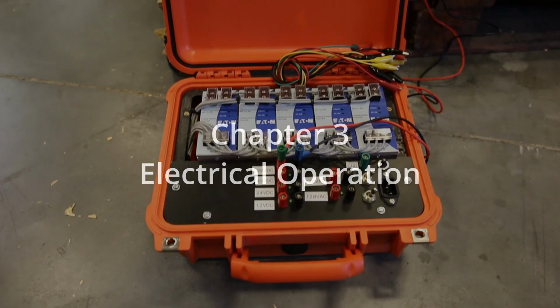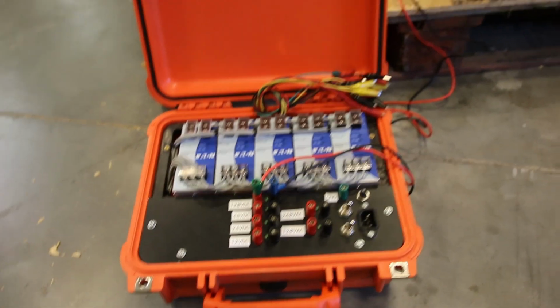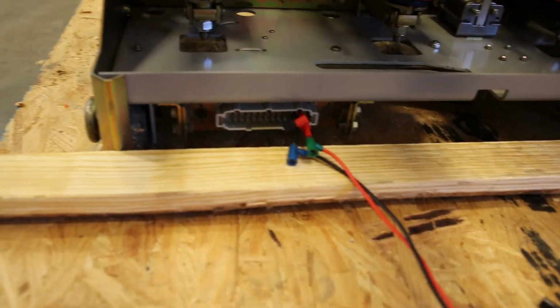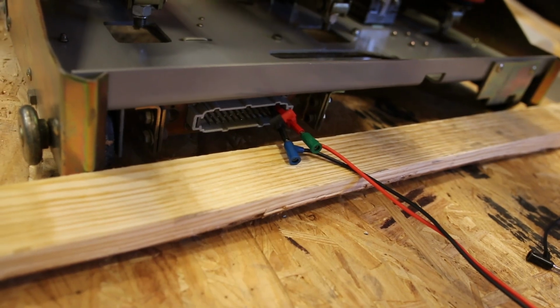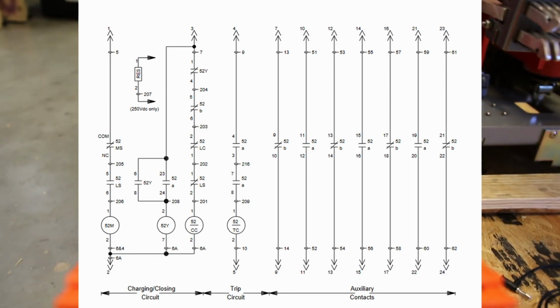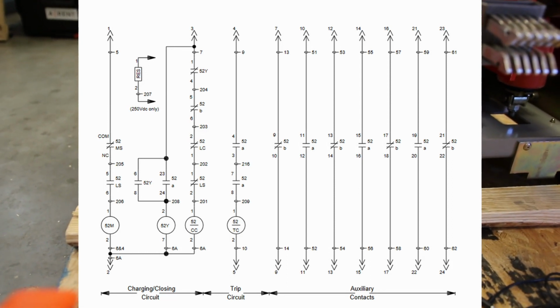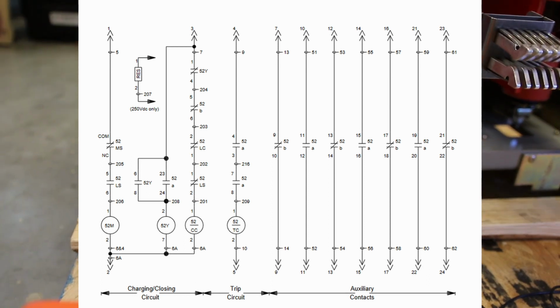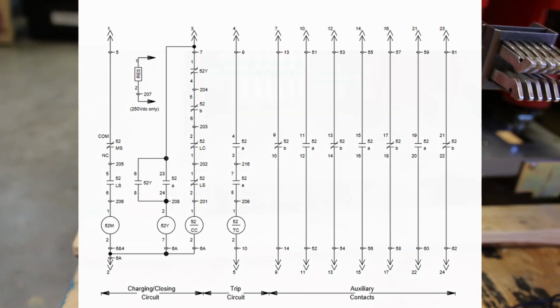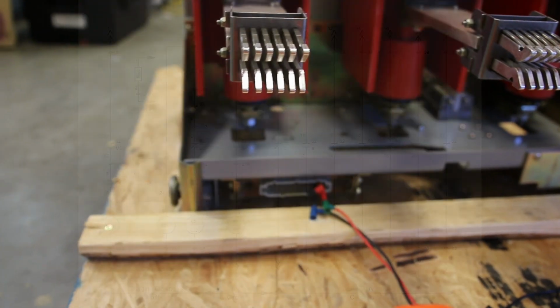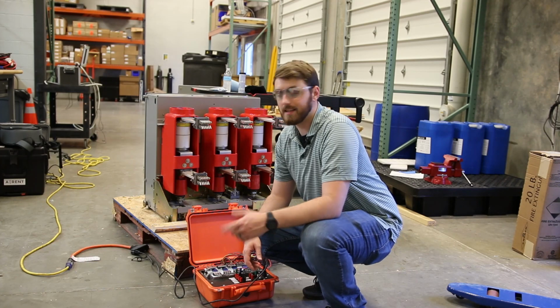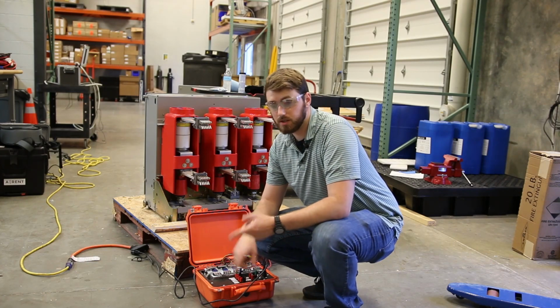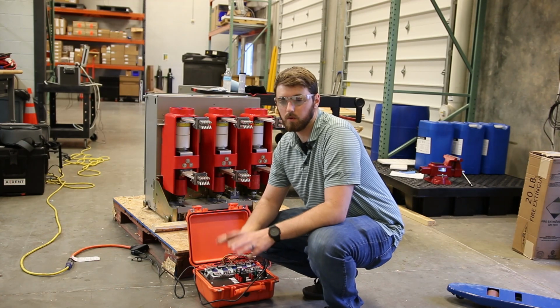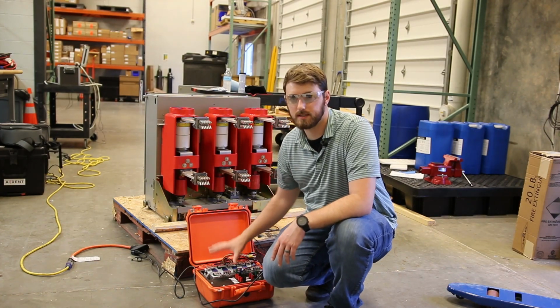Don't mind my super sketchy test set. This is a home-built 120 volt DC power supply. Works a treat. Obviously we're hooking up onto the secondary block. This is where the controls from the cell would come in, and we're connected straight to the pins. There's definitely better ways to do this. If you had a female section of the secondary block out of a switchgear or a test umbilical, that would be a lot better. I don't have one since we're doing this in the shop, so this is what we got. This breaker runs on 125 volt DC for the charging motor, the trip, and the close. So we're going to operate that with this 120 volt DC power supply.